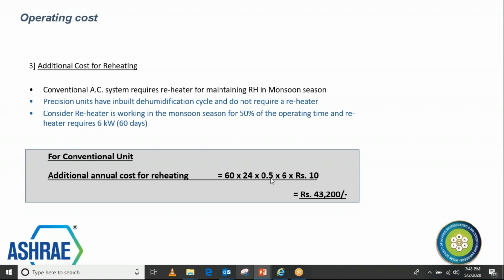So if you see here, 60 into 24 into 0.5, only 50% of the time we have considered heating here for 2 months, and 6 into 6 kilowatt of heater, and 10 rupees is again the unit rate here. So 43,200 is what you are losing on the heating because of the reheating.